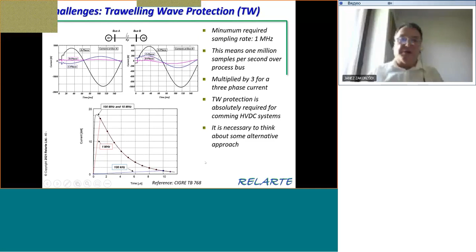So this means that we need to send 1 million samples per second over the process bus. And if we multiply this by 3 for three-phase currents and maybe add some voltages, this is impossible to reach even with the most modern technology possible. So there are different ways maybe to do this. They were discussing that they should maybe detect the traveling wave in the merging unit and send a signal to the relay, but I don't like this approach because I don't think it is good enough.